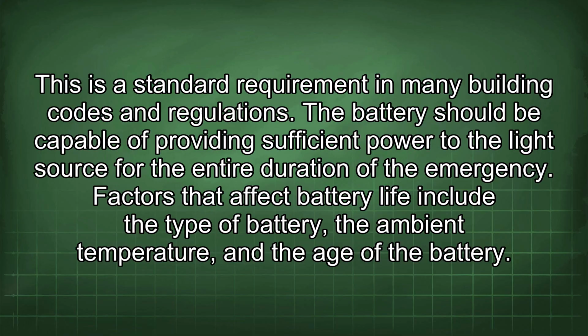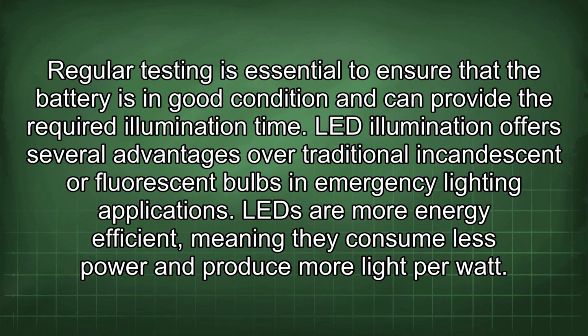The battery should be capable of providing sufficient power to the light source for the entire duration of the emergency. Factors that affect battery life include the type of battery, the ambient temperature, and the age of the battery. Regular testing is essential to ensure that the battery is in good condition and can provide the required illumination time. LED illumination offers several advantages over traditional incandescent or fluorescent bulbs in emergency lighting applications.